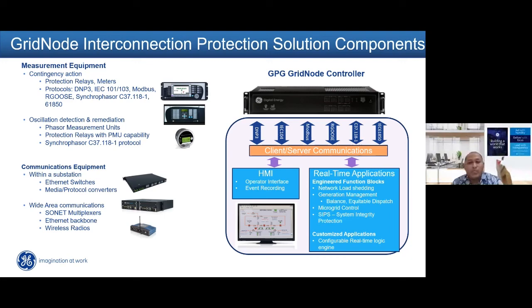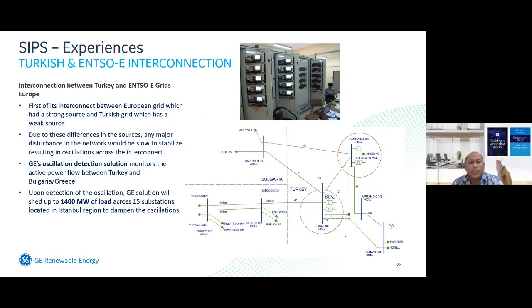So here are the experience and references of GE SIPS projects in the past. Here is a reference in the Turkey and ENTSO-E interconnection, which is the interconnection between Turkey and the ENTSO-E grid in Europe. First, it interconnects the European grid, which has a strong source, and Turkey's grid, which has a weak source. Due to these differences in the source, any major disturbance in the network would be slow to stabilize, resulting in oscillation across the interconnect. So the GE oscillation detection solution can monitor the active power flow between Turkey and Bulgaria and Greece. Upon detection of the oscillation, the GE solution will shed load of up to 1,400 megawatts across 15 substations located in the Istanbul region to dampen the oscillation.